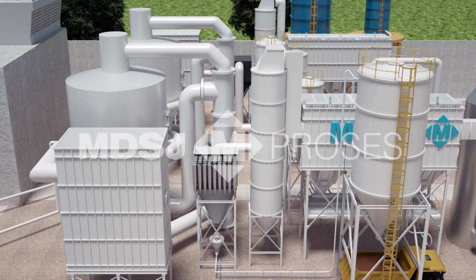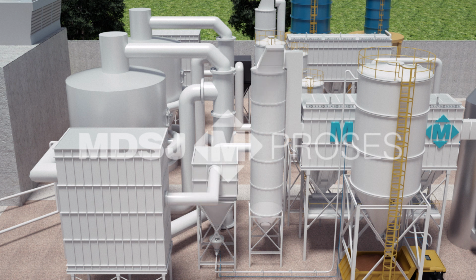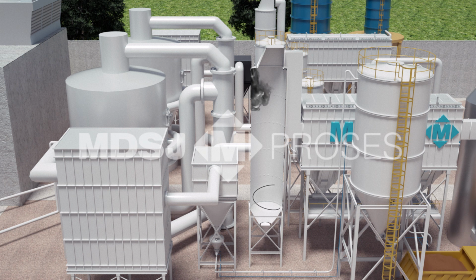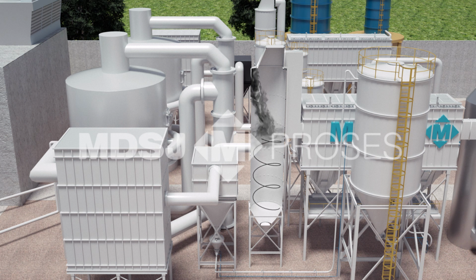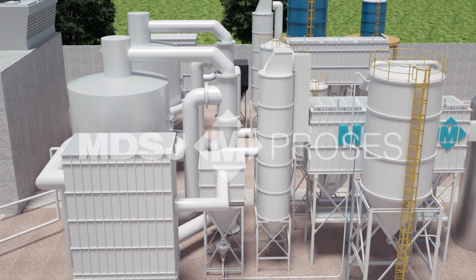Flue gas containing dust and particulates from the waste heat boiler goes through a series of multicyclones for particulate reduction. The removal of hazardous materials present in the flue gas, such as mercury, dioxins and furans, is achieved by the injection of active carbon after the multicyclones. In addition to active carbon, lime is also injected to remove acidic compounds such as SO2.